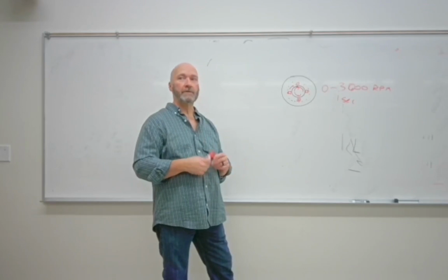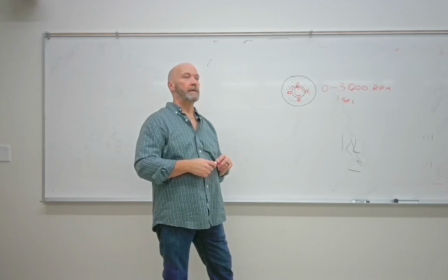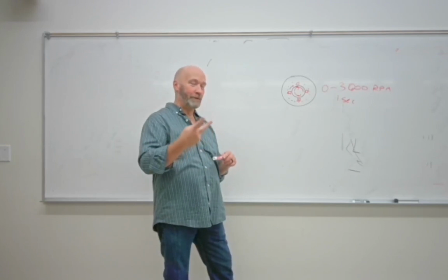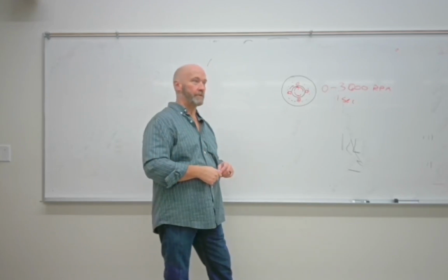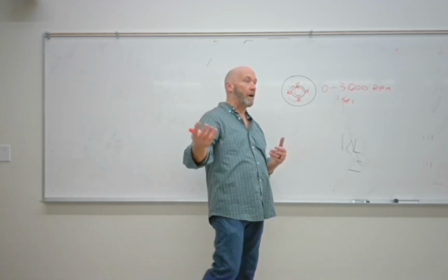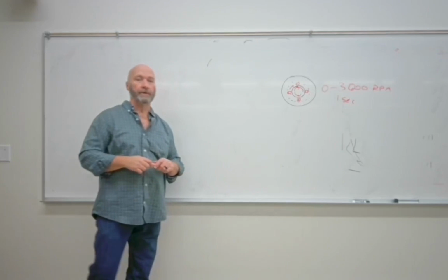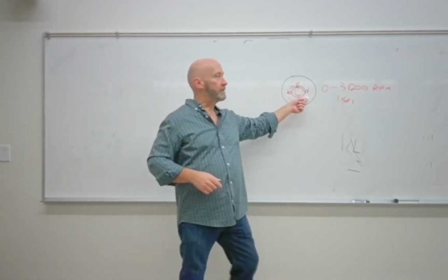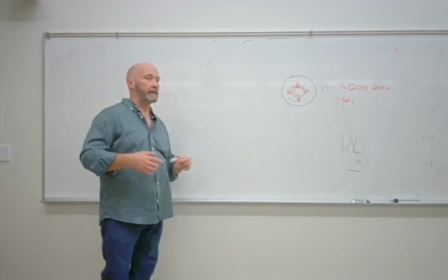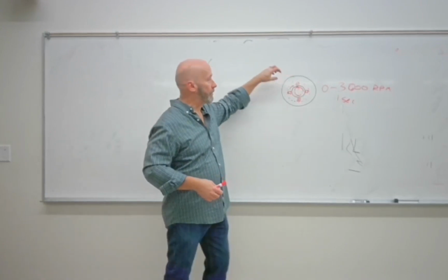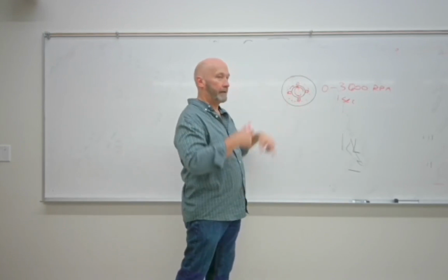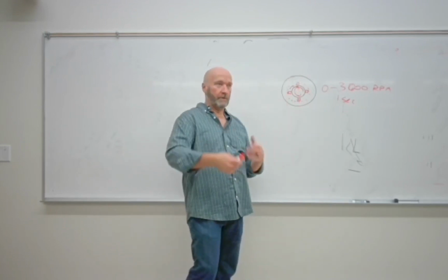So why is that? It's friction. What's friction cause? Heat. What's the main thing that kills an X-ray tube? Heat. Right. So now we've got two different places where heat becomes an issue: the bearings, and also the heat that we create on the filament and deposit on the rotor. Okay. Induction mode. 0 to really fast in 1 second. It spins backwards to kill it, but it works off of electromagnetic induction. We use electricity to create electromagnets to drag a magnetic field around and around and around to turn a rotor.